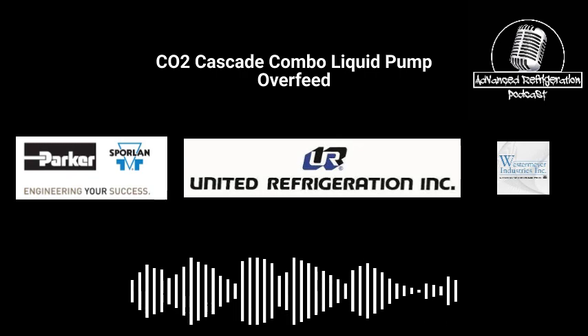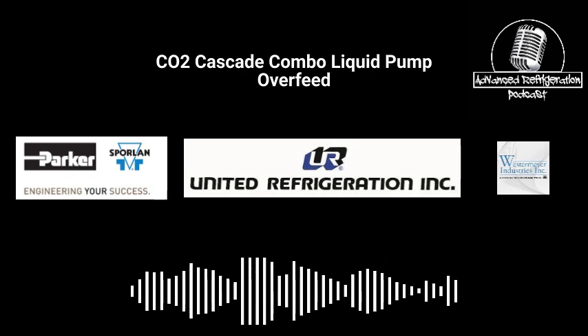They're trying to get rid of the higher GWP refrigerants. Unfortunately, right now in California, you can't have anything over 150 GWP, and if it's over, it can only be 50 pounds. That's why they're trying to reduce the amount of refrigerants, and why they're coming out with all these lower GWP refrigerants. Even with that lower GWP stuff, in California you're pretty much screwed. It shuts cascade out because the cascade is going to be more than 50 pounds. So those areas are being forced to CO2. Can you even install a supermarket that's not CO2 in California? I don't think so. I really don't think so.